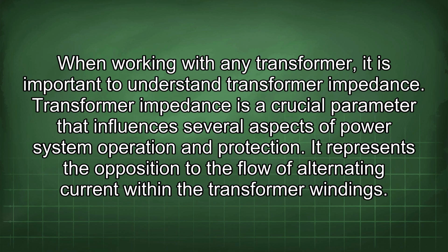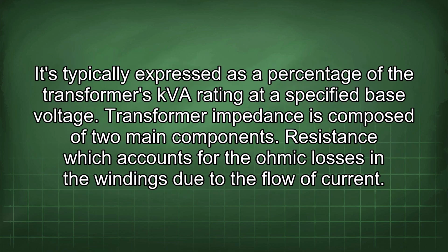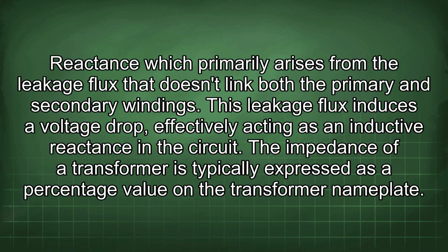Transformer impedance is a crucial parameter that influences several aspects of power system operation and protection. It represents the opposition to the flow of alternating current within the transformer windings. It's typically expressed as a percentage of the transformer's kVA rating at a specified base voltage. Transformer impedance is composed of two main components: resistance, which accounts for the ohmic losses in the windings due to the flow of current; and reactance, which primarily arises from the leakage flux that doesn't link both the primary and secondary windings. This leakage flux induces a voltage drop, effectively acting as an inductive reactance in the circuit.